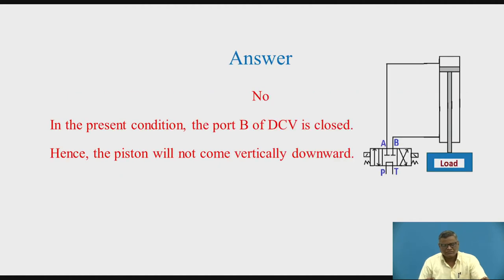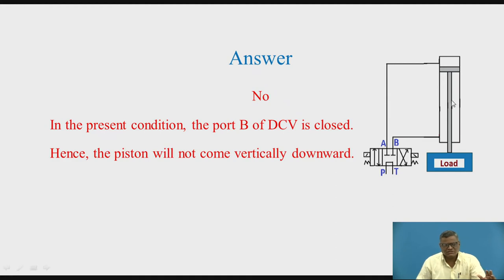In the present condition, you have to check the spool position — it is in the middle. If the piston has to come vertically downward, the oil from the rod end side should be going to the tank. But port B is closed. So the load is not going to come vertically downward, and the piston is not going to come vertically downward, but it is exerting pressure to some extent presently. That is the answer.